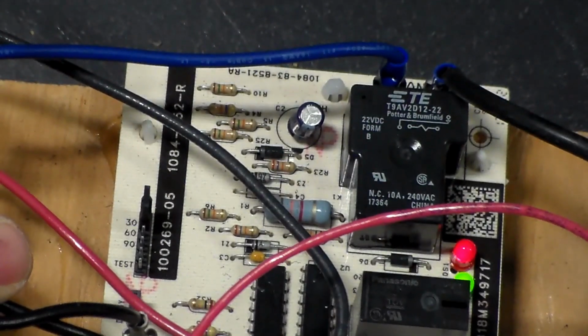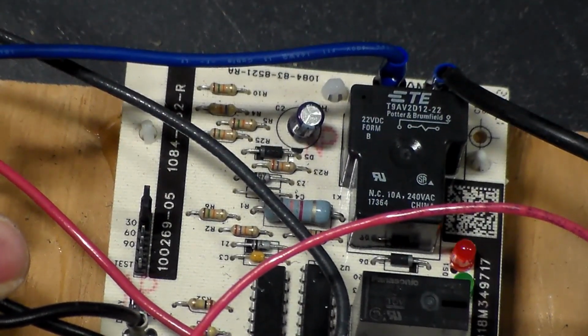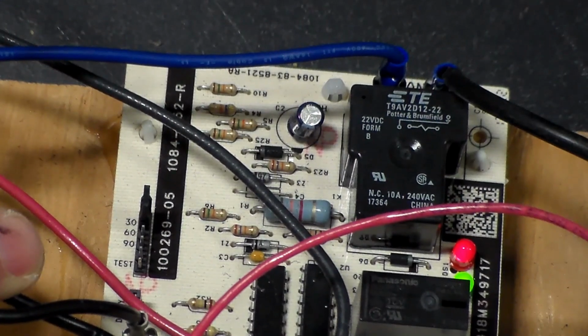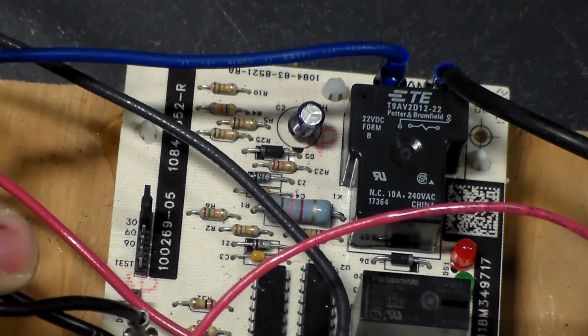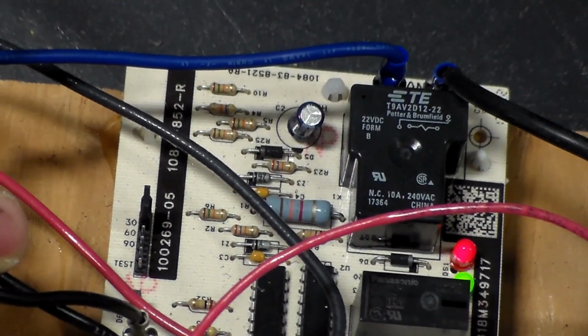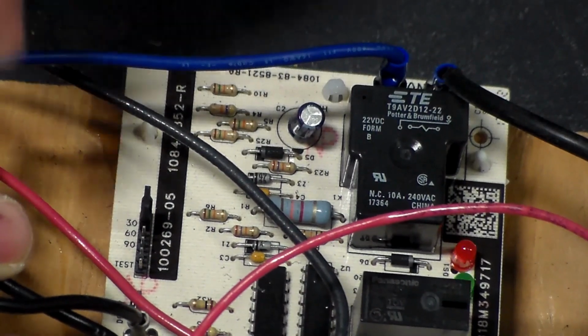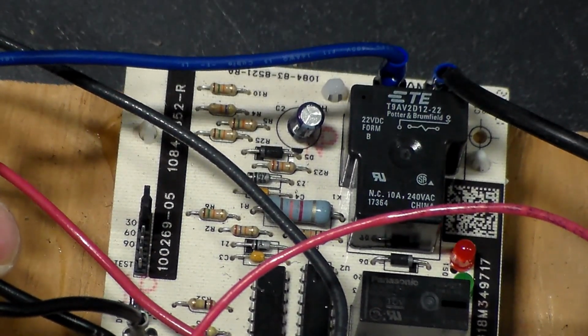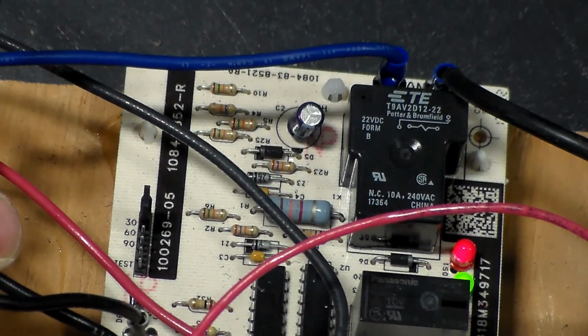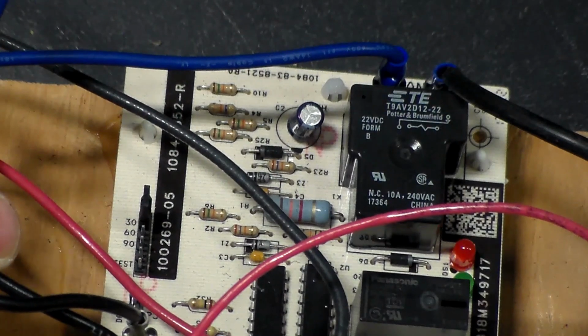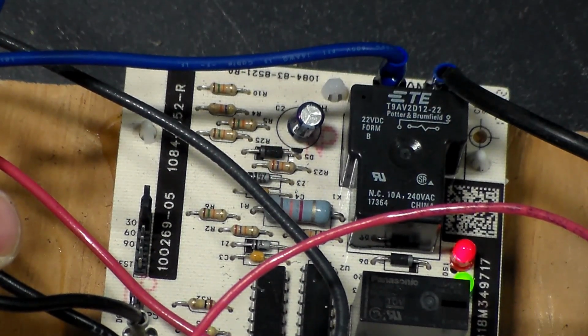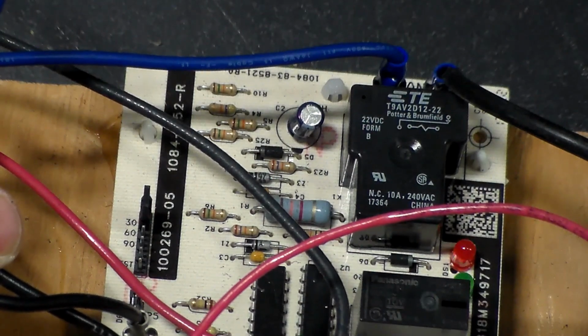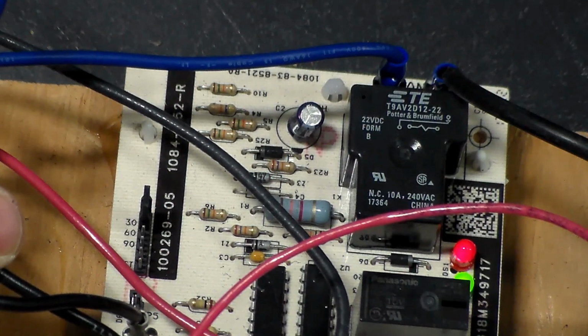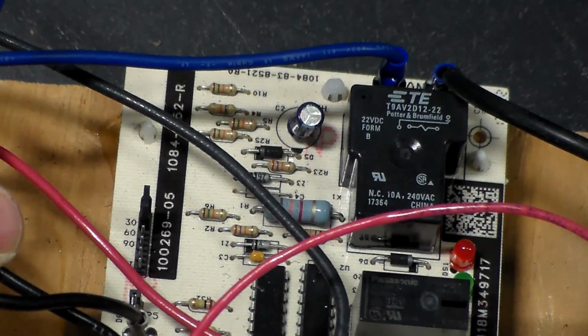I've seen people make this mistake in the field, and what they've done is they've made the problem worse. They roll up on a heat pump and it's an ice ball, and they're used to having defrost timers in refrigeration where you can set the amount of defrost time. They see that it's set for 30, and they say, oh, the problem is it's not running in defrost long enough, so I'm going to change it to 60. What they've actually done is made the problem worse, because these heat pump boards have a built-in timer of 10-minute long defrost. That's not adjustable. It's not something we can adjust.